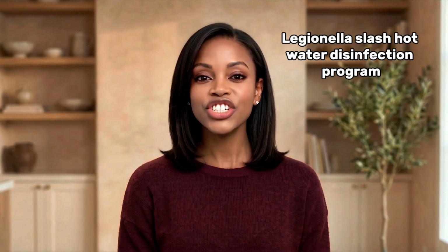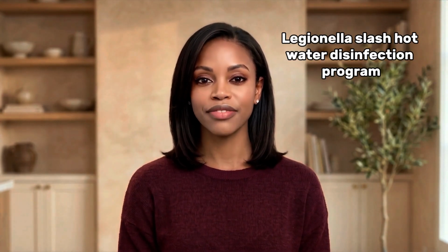Setting 9. Legionella/hot water disinfection program. If your system stores domestic hot water, it needs an appropriate strategy for controlling the risk associated with Legionella bacteria. Depending on the hot water system, you may see something called Legionella protection, disinfection, thermal disinfection, or another similar term. Some systems periodically raise stored water temperature above the normal DHW target as part of that strategy.